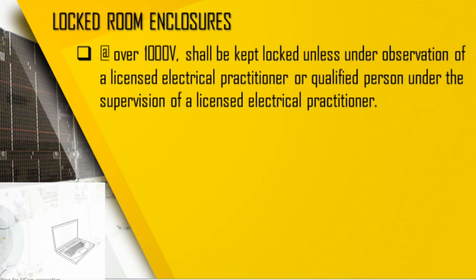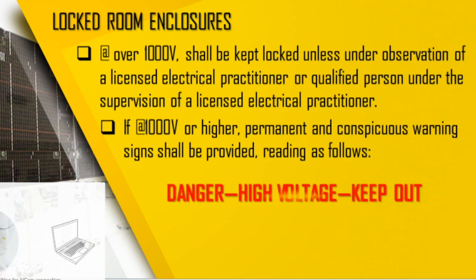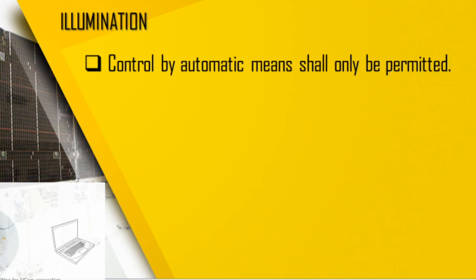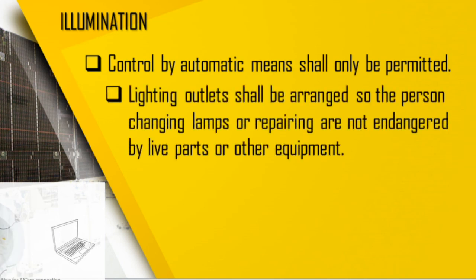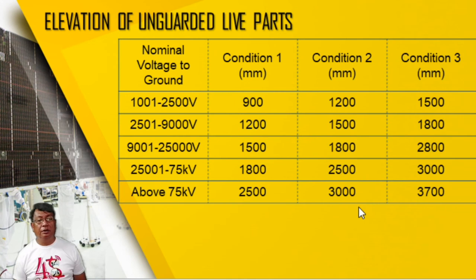Okay, so next we have, if over 1000 volts, permanent and conspicuous warning signs shall be provided as follows. Control by automatic means shall not be permitted. Lighting outlets shall be arranged so that persons changing lamps or repairing are not endangered by live parts or other equipment. And then another one here. Okay, so that is elevation of unguarded live parts, no? So we have that.